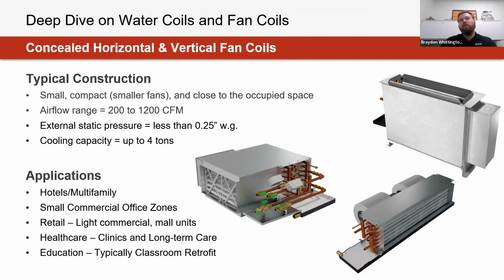And one thing you'll notice even for this horizontal style, as a lot of times ceiling space is at a premium, is that it's more of a restriction on what its maximum height is going to be. So they build out its overall width. The reason for that, as we learned during our water coil class, is that by increasing its width, we're maximizing and adding a bigger coil face area for heat transfer and a lower pressure drop on the fans that are paired with this equipment.